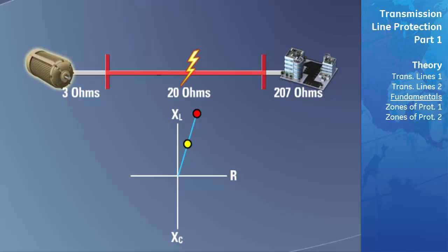Since the distance that the relay measures to the fault is actually closer than the length of the entire transmission line, the fault is in the zone that the relay is protecting. Therefore, the relay will send a signal to trip the breaker to clear the fault. The trip of a transmission line breaker normally initiates an auto-recloser sequence that works in conjunction with the synchro check function. The auto-recloser and synchro check functions are covered in detail in the distribution section of the CD.